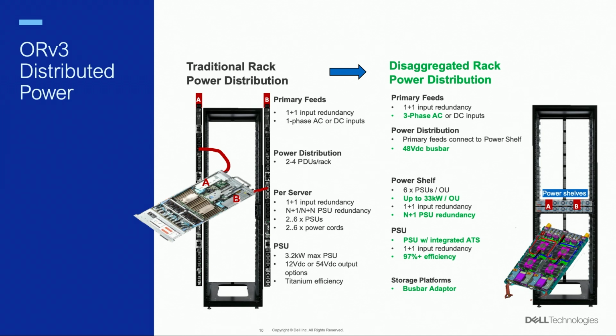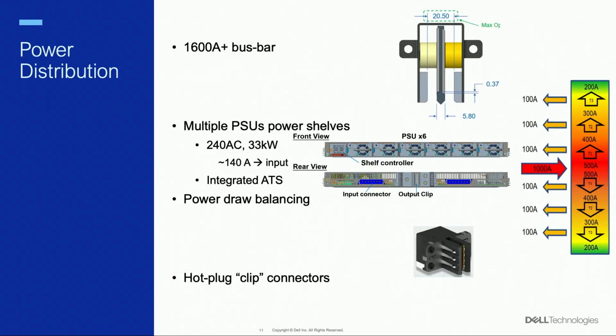it's much more efficient. With Open Rack V3 we have three-phase or direct current connecting directly to the back of the power shelves, and the distribution happens through the bus bar that you see depicted at the top of this slide. The power shelves have their own management so that you can configure the power, and they can sustain up to 33 kilowatts in n plus 1 mode, so they are already redundant. They have an integrated automatic transfer switch, and they automatically balance the power draw through the bus bar. What you see at the bottom of the slide is the connector within each server to get the power from the bus bar.